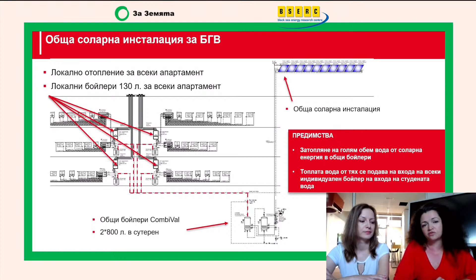There should be a system with common boilers which lead the water to the local boilers in each apartment. If the water is warm enough, it's directly used. If the sun is not strong enough, for example in winter, only then is the local energy source, the thermal pump, turned on to heat the domestic hot water. This considerably decreases costs for domestic hot water and provides an interesting aspect that can be integrated in new buildings and retrofitted buildings.